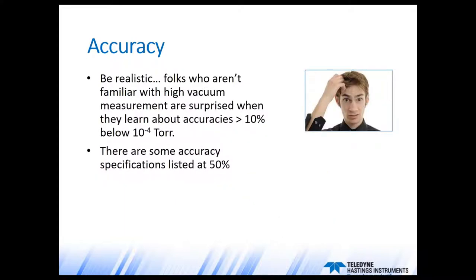One other thing about accuracy: some metrology managers are very surprised when they find out that a gauge has an accuracy specification of 10% of reading or higher. Vacuum gauges, especially high vacuum gauges, are not like micrometers or electrical meters. I've seen some accuracy specifications for vacuum gauges listed as high as 50% of reading. So be realistic about the spec that you're asking for.